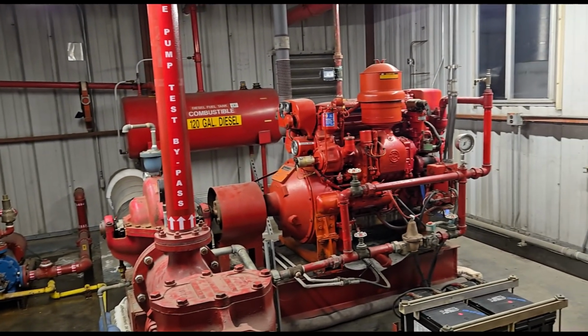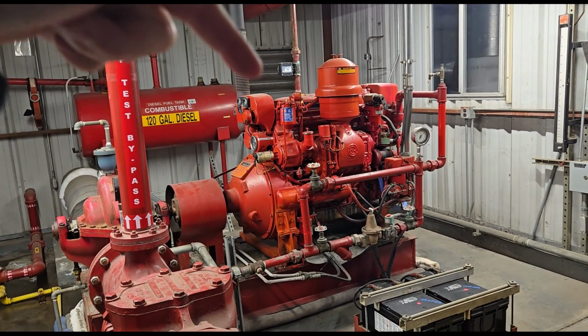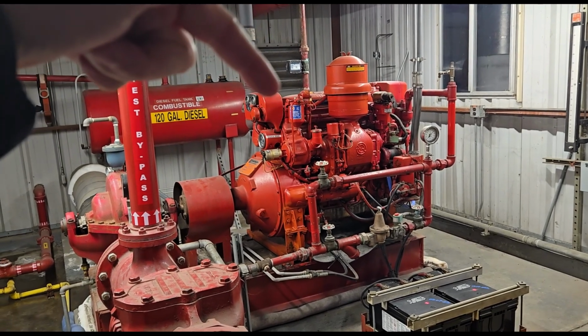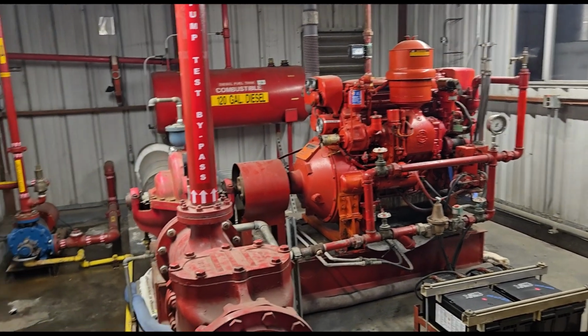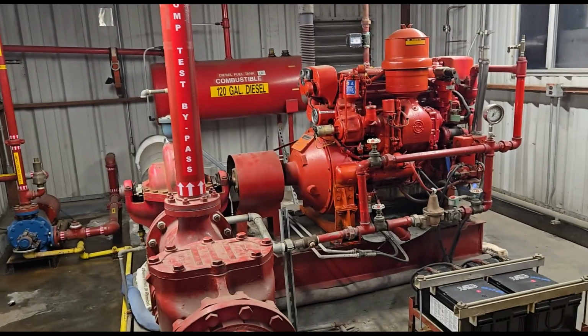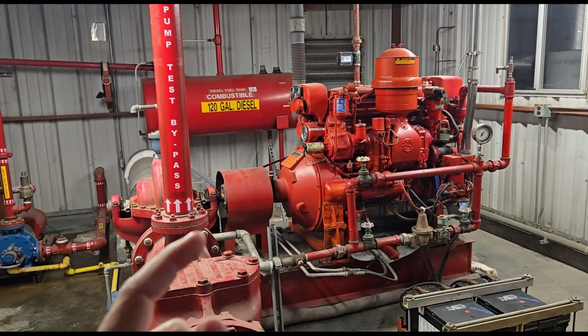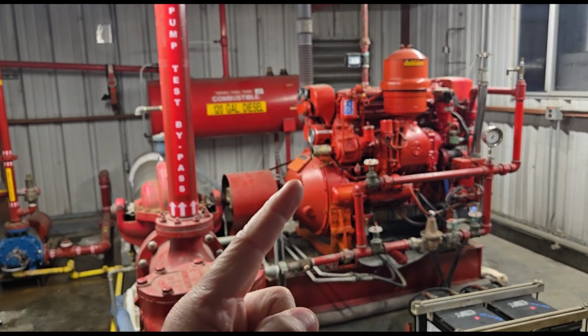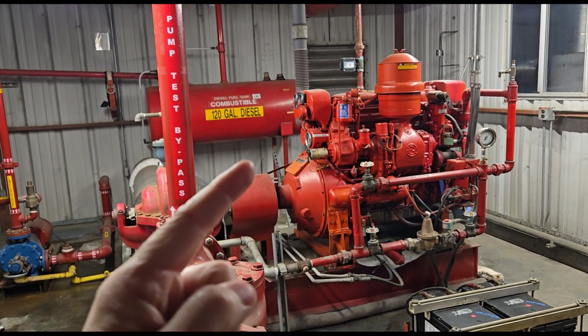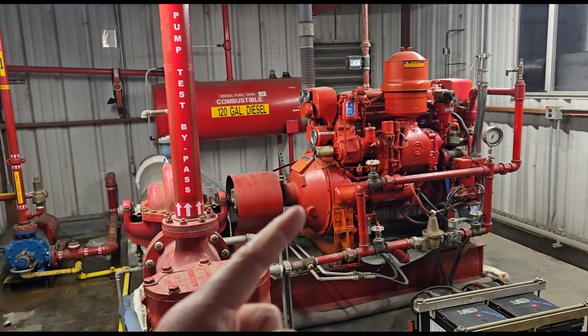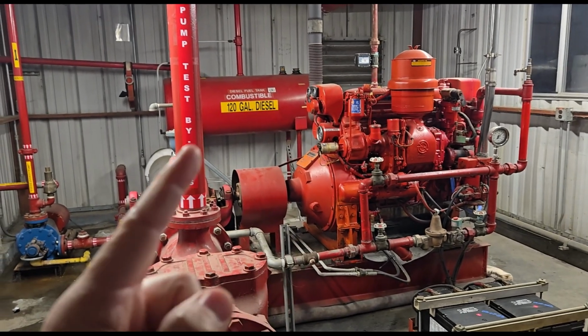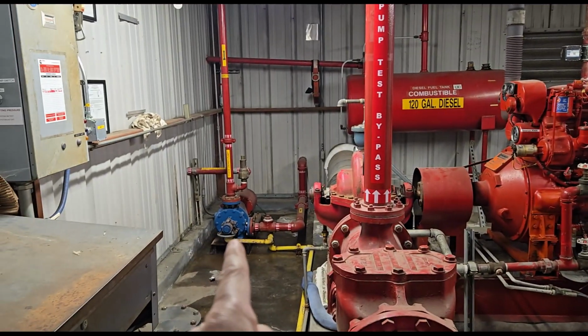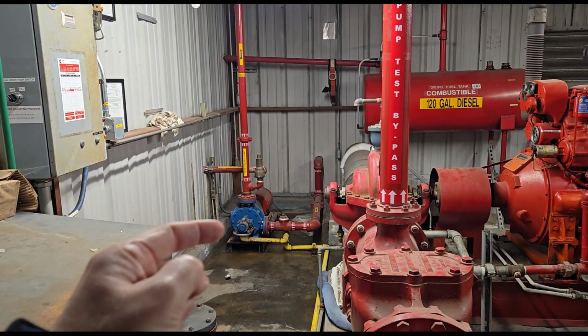So again, your sprinkler company is usually the one responsible for doing your pump testing. I'm with the alarm company. We're just doing electronic device testing. This client has a different contractor for their pump testing and their sprinkler testing. So we're not responsible for running this pump, and we're not going to take liability for running this pump, so we're going to switch it off, and we're going to run everything off our little jockey pump over here.